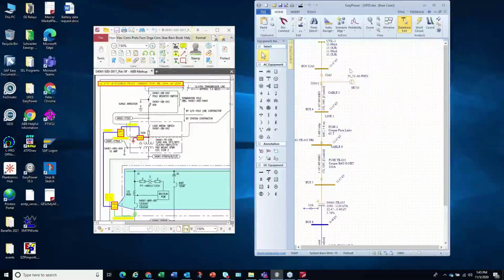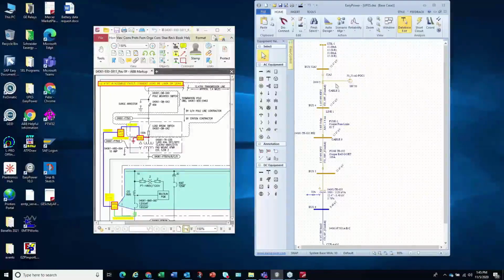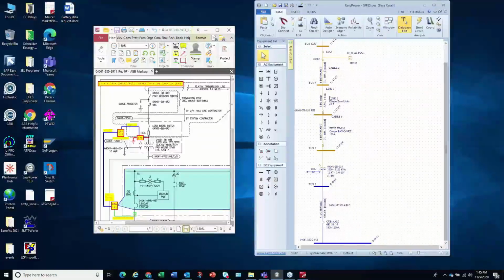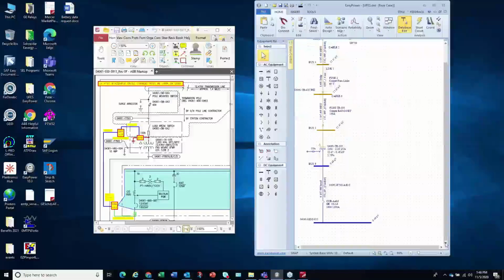So we'll see there's a utility source at 12 kV coming down through a substation that you don't see out there, the line. Then there is the pole top fuse link, 65 amps, and then there is a bayonet current limiting fuse installed in the pad mount transformer itself. And then on the secondary of the transformer, we have a cable that takes us to the low voltage switchgear, and the main breaker is what we're focusing on here.